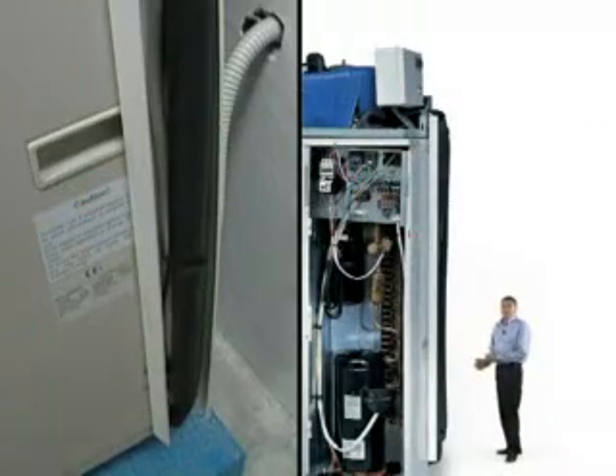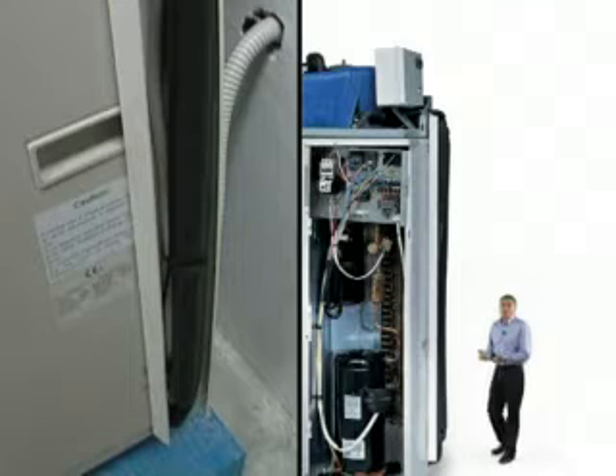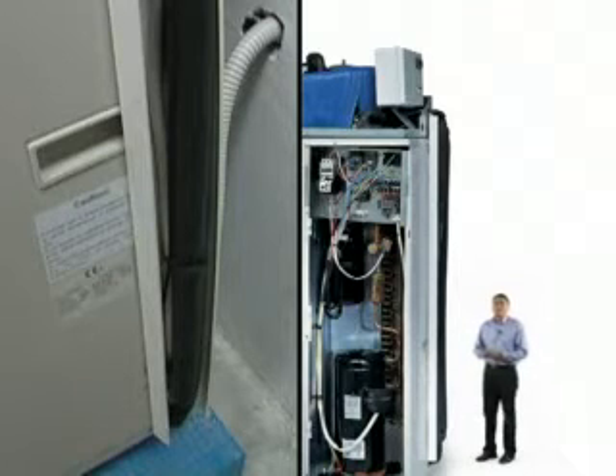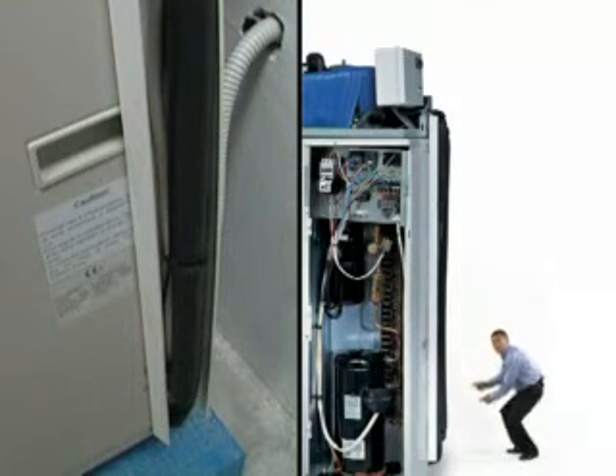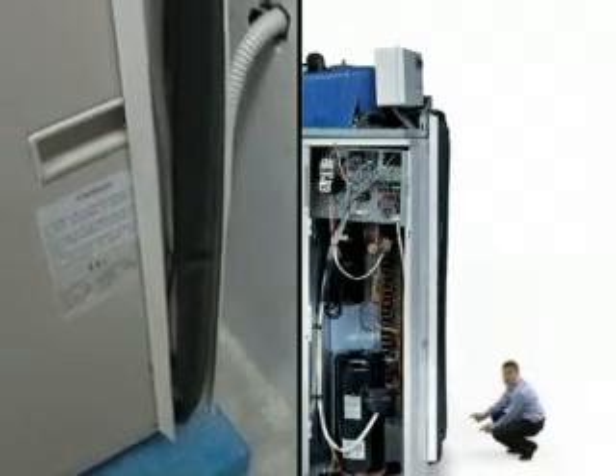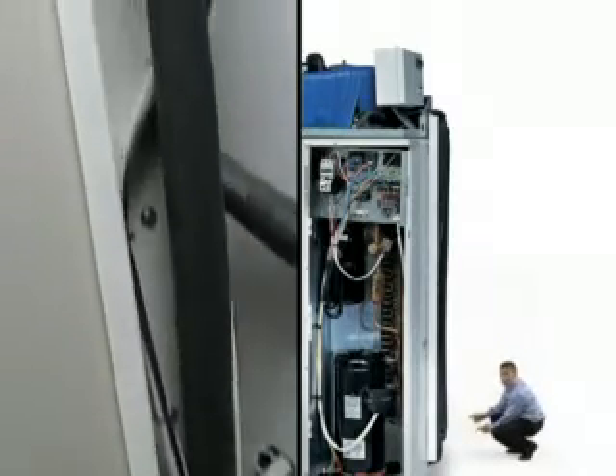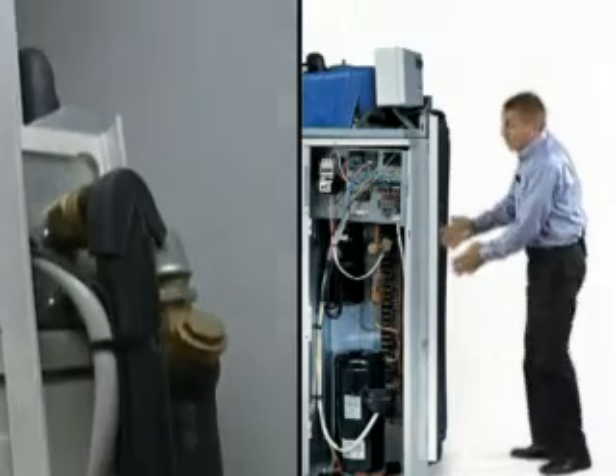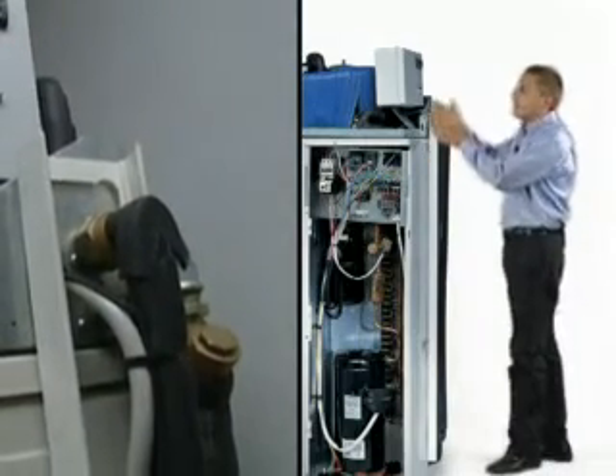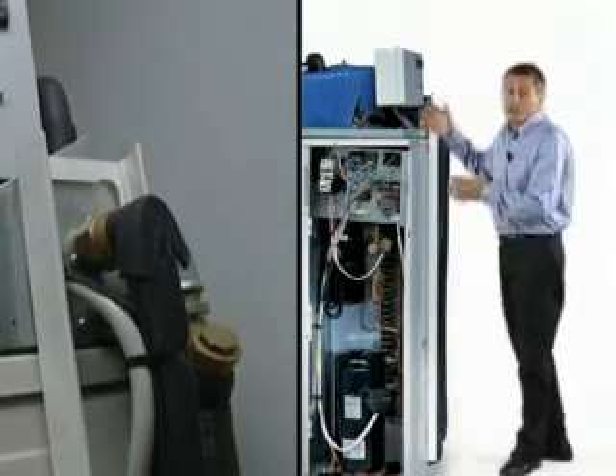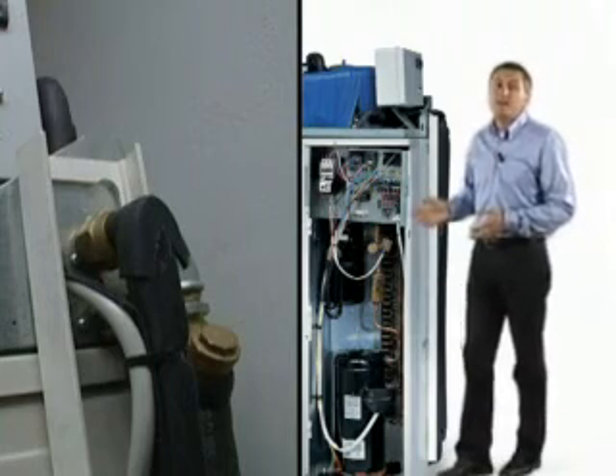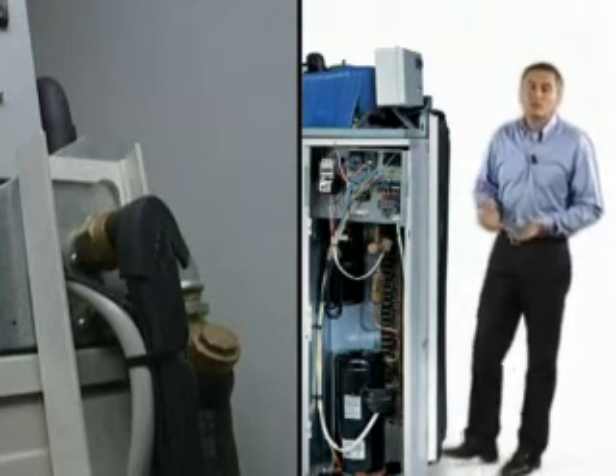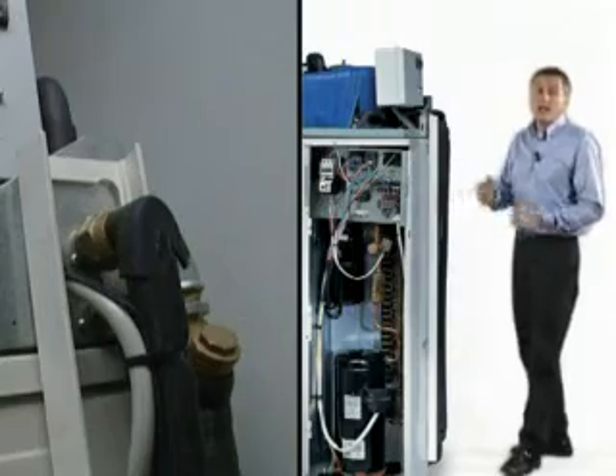Now we'll see the Climabox operation for the water-gas unit. At this point, we notice the gas pipes that start from the motor condenser. They run through the machine itself and connect to the water exchanger of the additional unit. Gas and water circulate inside the exchanger.